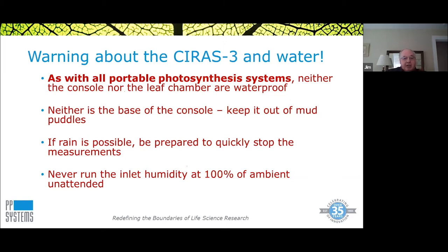Another message here is never run the inlet humidity at 100% of ambient if you're not going to be there next to the instrument, because at times the environment can change suddenly. And when your gas exchange is going fine and the environment changes quickly, you can very easily get into a problem of condensation inside the leaf cuvette.